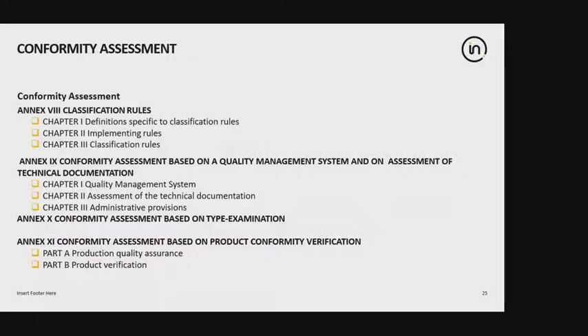Now, once you have decided the classification of the device, which class it falls in, you can also choose from 3 possible ways of achieving the CE marking, the conformity assessment system. The conformity assessment system has been discussed in Annex 9, Annex 10, and Annex 11 of the medical device regulation, which prescribes the methodology of how you can achieve compliance, or how you can achieve the certification towards CE marking.